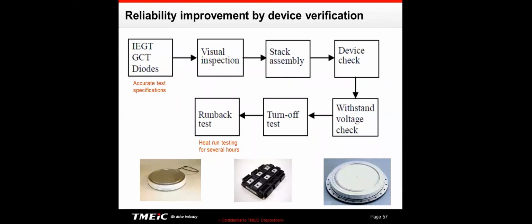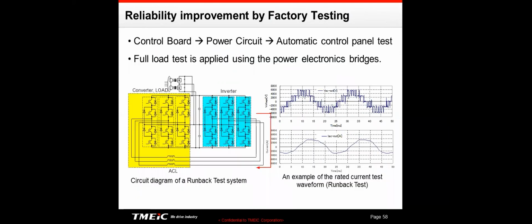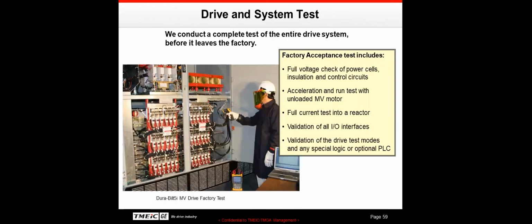Here's some of the tests that you can do for increased reliability. We generally can afford to do much more extensive testing on a medium voltage drive than these low voltage drives that are running off the assembly line, although many low voltage drives get tested pretty well as well. Here's some more reliability improvement by testing of the components and testing of the input waveforms and the output waveforms. And then we do a complete drive and system test using a real motor.